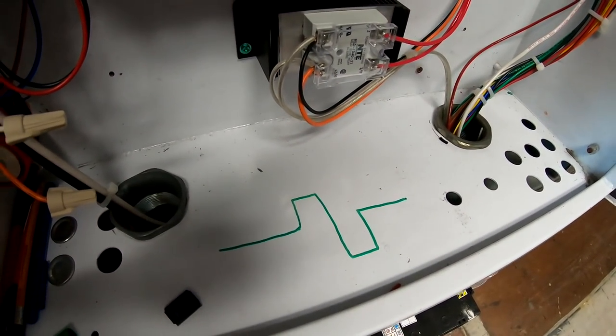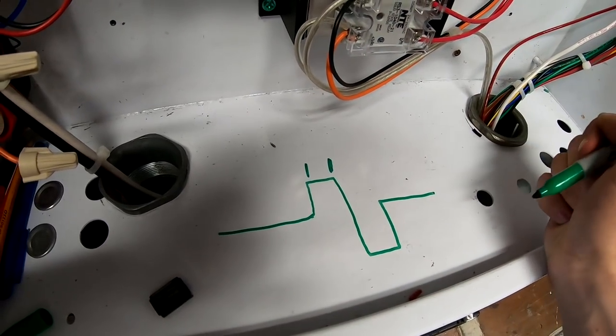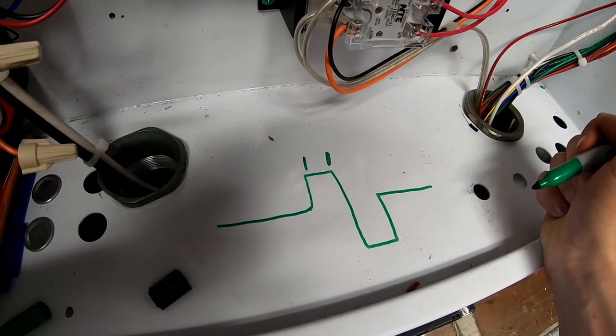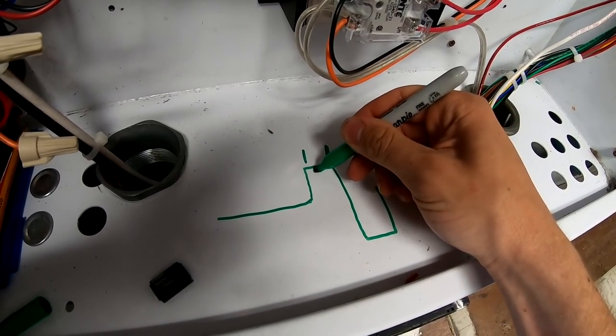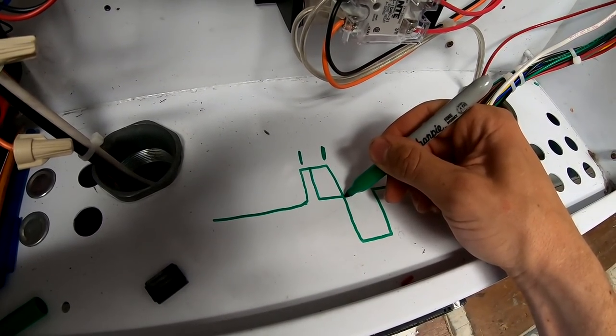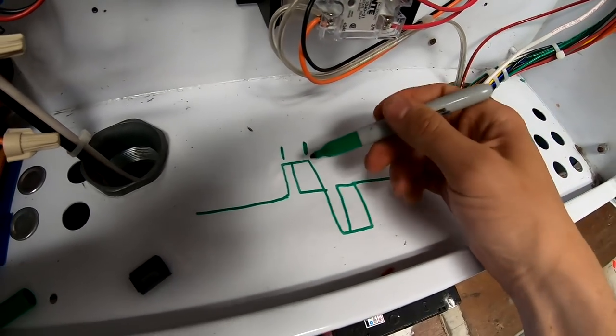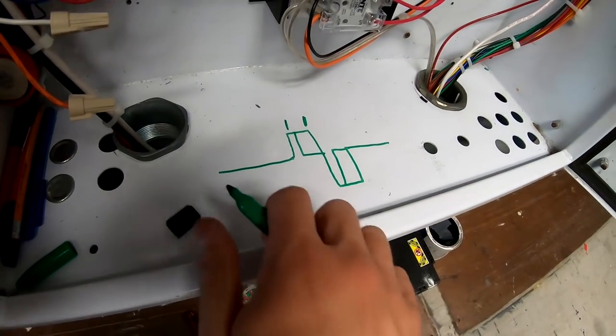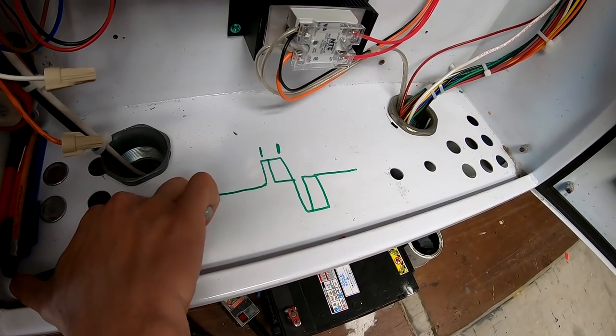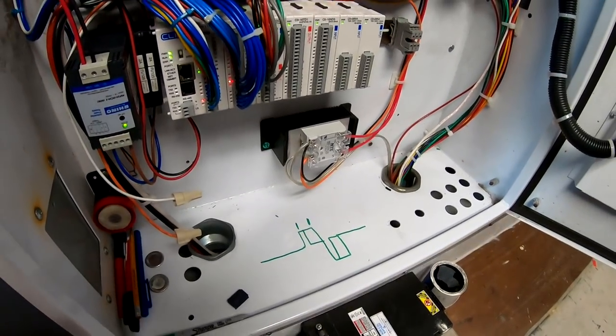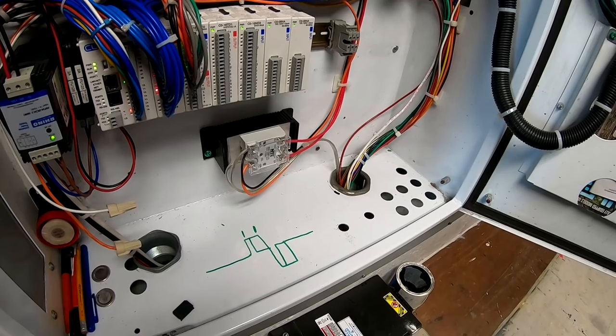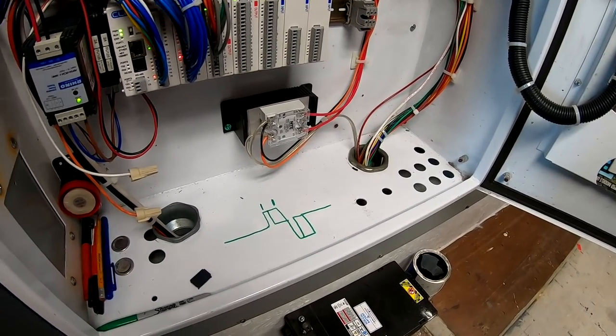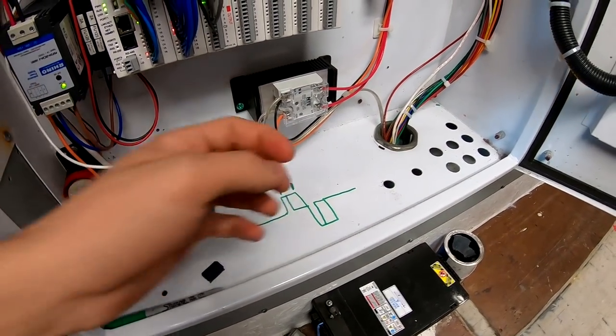So a couple of things happen. That signal is opening and closing this really quickly. So if you were to imagine, I'll draw it out. You have your square wave and it looks like this, right? So what that signal is, is how big this is right here, the amount of time that that's on, versus if it were to just be, you know, if it were to come back down here and then be spread out, come back up here. This allows varying amounts of power to go through, so we can vary and have a percentage of the time that that's on. And that allows us to only allow a couple of watts to go to the spa or full wattage depending on how wide this part of that waveform is, and that's how long the solid-state relay is on for.